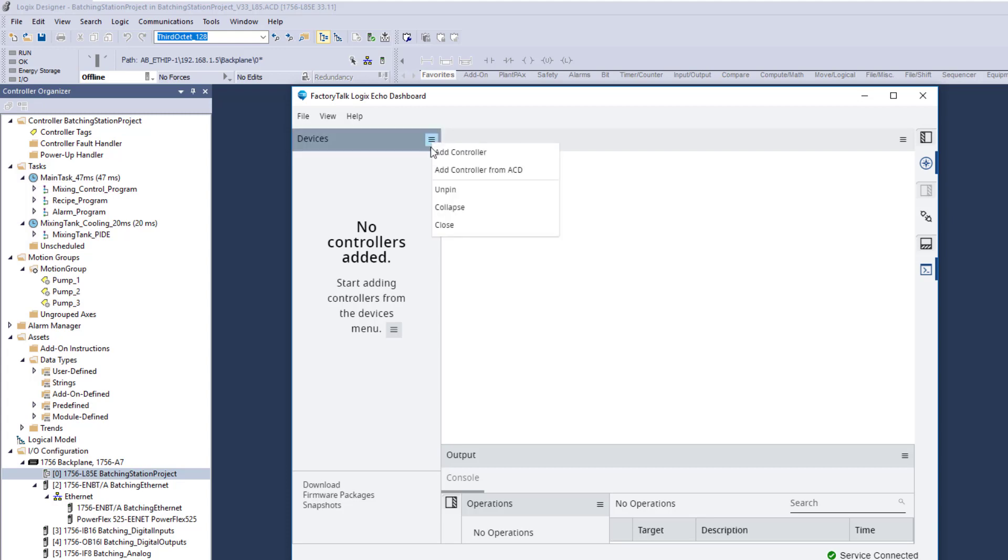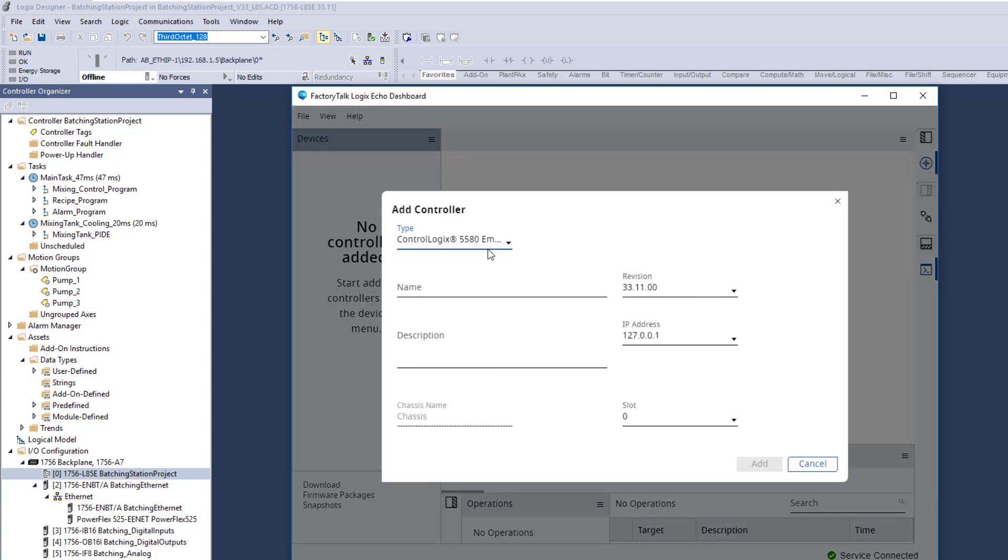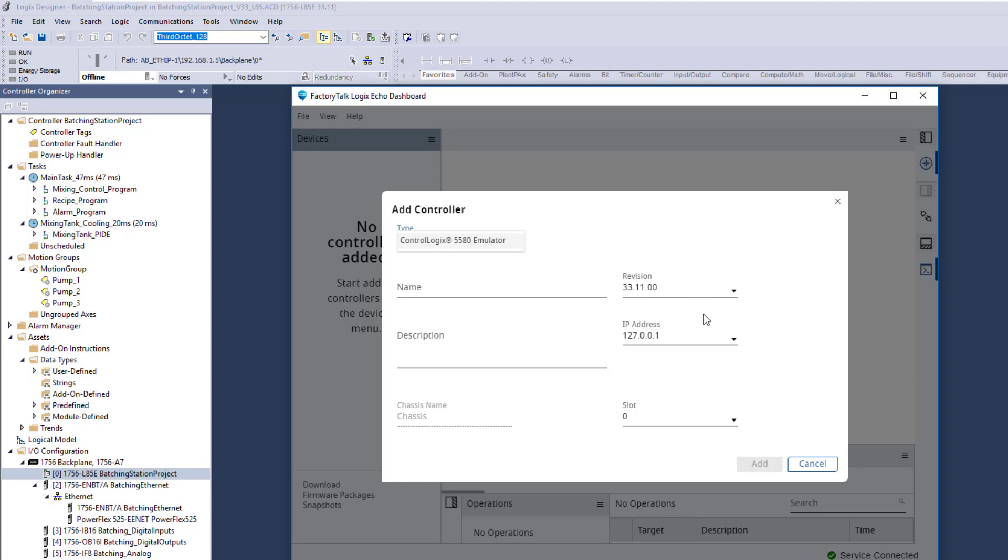So when we come up here and we go to devices, we can add a controller. So when we add a controller, it's going to show you that it only does a ControlLogix 5580 emulator. And the current versions that are basically what you have installed on your computer are going to be 33 and above. So think about this is going to be L8 processors and above. If you're using anything less than L8, you're going to use the standard process of what we used to use as far as emulation. I have tons of videos showing you how to do emulator. This is moving forward using Project Echo where you don't have to change a single thing.